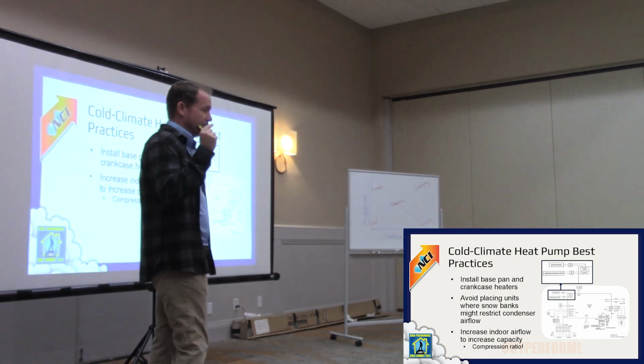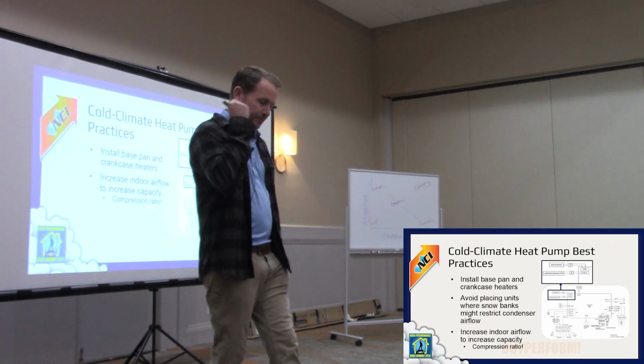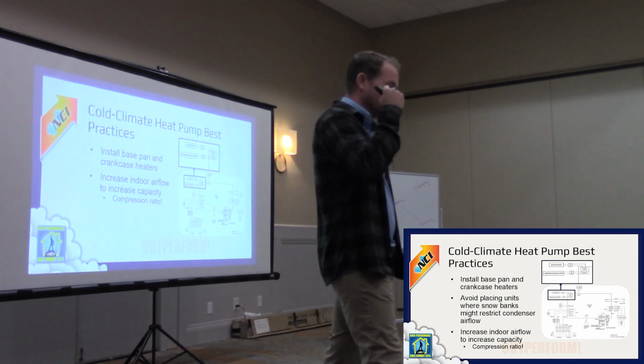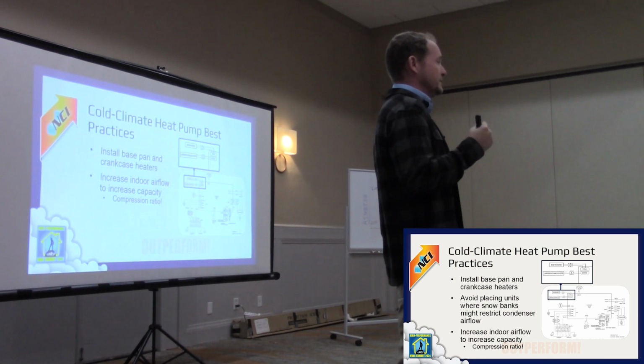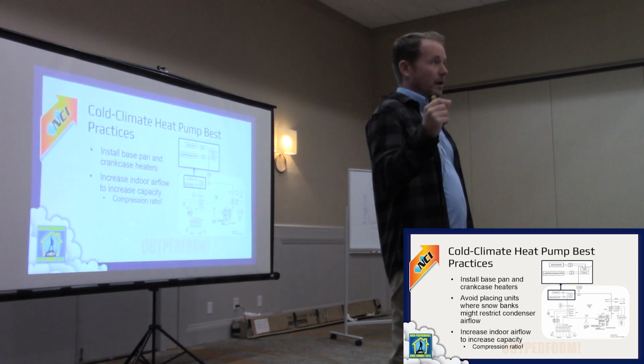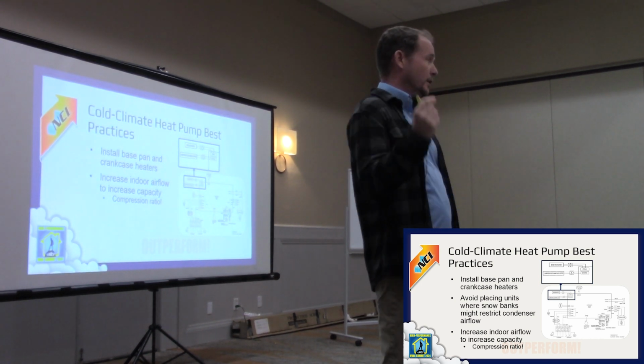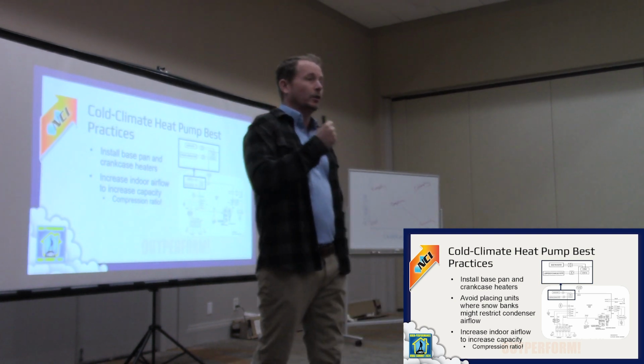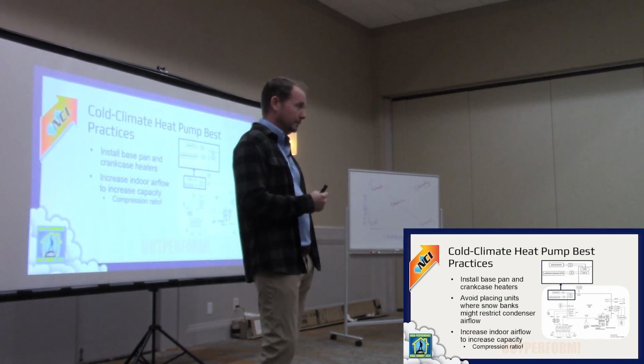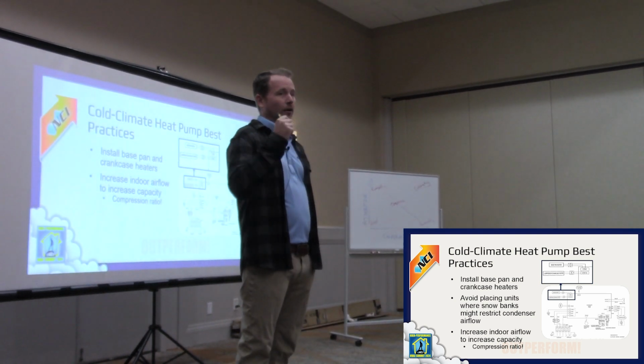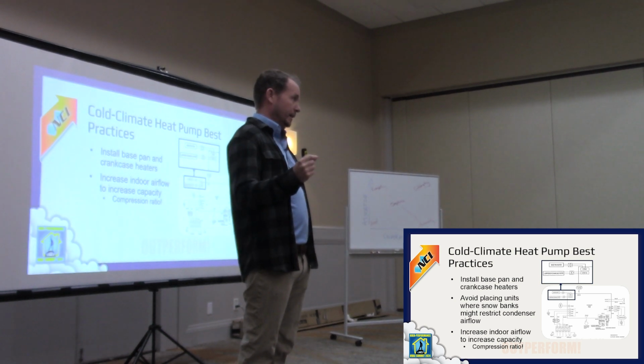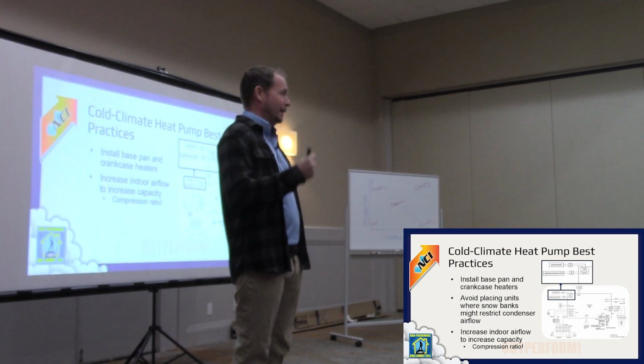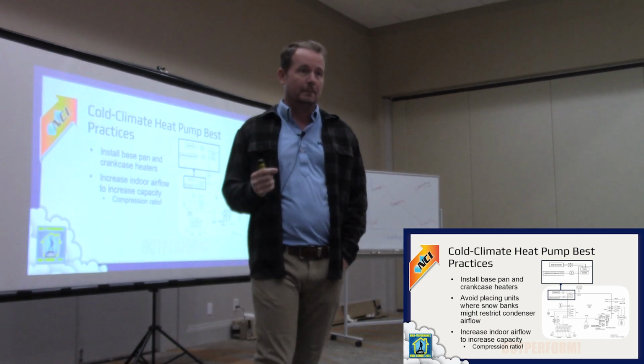The next thing I want to mention is how you get better results out of cold climate heat pumps in terms of capacity and efficiency. That is to run a lower compression ratio. And how do you run a lower compression ratio on a cold climate heat pump? By bringing more air over the indoor coil. Now what's the problem with bringing more air over the indoor coil on a cold climate heat pump?